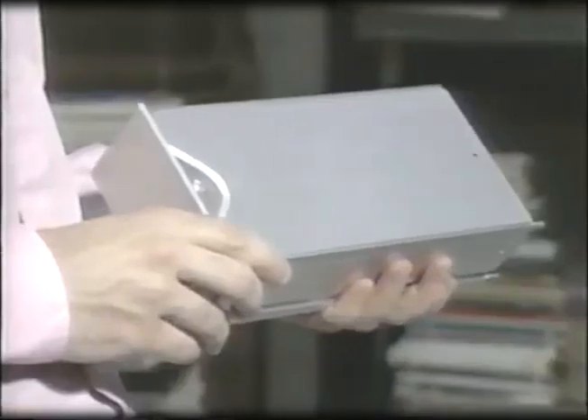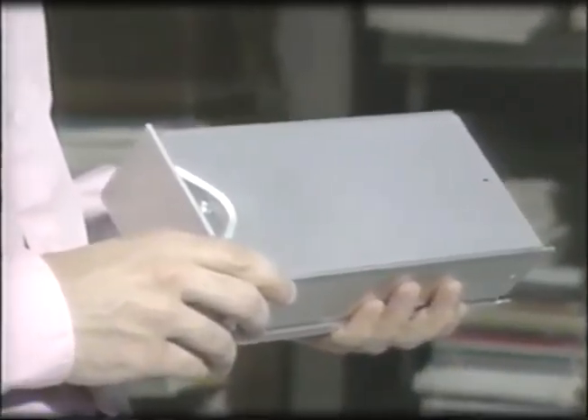Shields protect against radiated energy that can upset controllers. The perfect shield is a metal box with no opening, but that's impractical. The next best shield is a box well bonded at seams with properly treated openings. Cabinet seams should be welded, and openings should be covered with wire screen or a metal gasket. Unfortunately, that's costly. The good news is, it's not necessary in most cases. When is it necessary? If the controller is near an air traffic control radar, a broadcast tower, or a military installation, you'll want that maximum protection because electromagnetic interference is more of a threat.